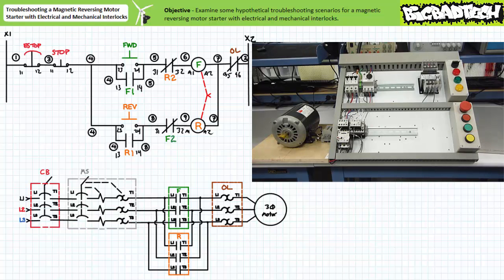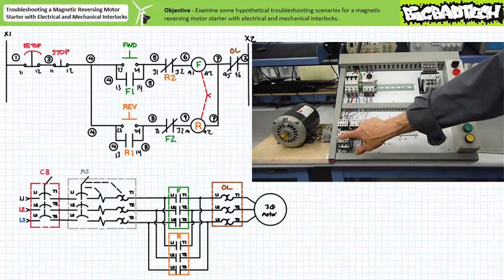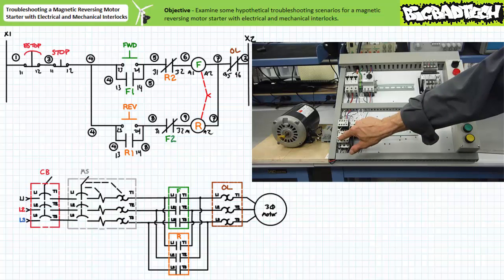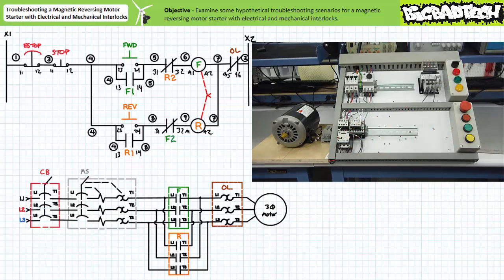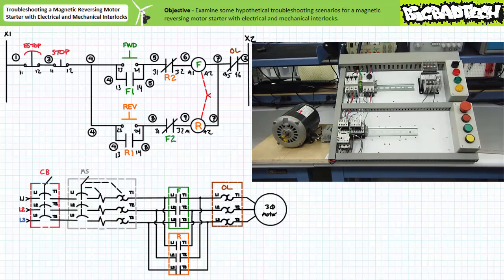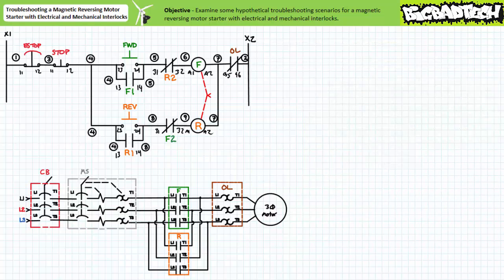In this case, I'm simulating an overload event by pushing the manual test button. The triggered overload element signals the forward contactor to open as expected. When the overload element in automatic mode cools and resets, i.e. when I stop triggering it, the system does not immediately return to the forward mode since the holding circuit is dropped out.